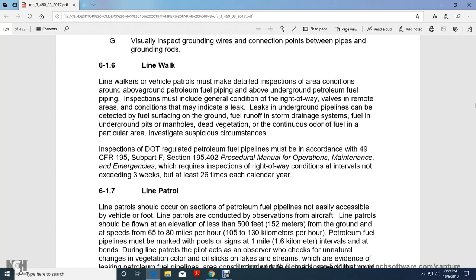Inspection must include the general condition of the valve and the remote area. Conditions that may indicate a leak of the underground pipelines can be detected by fuel surfacing on the ground, fuel in the runoff, the storm drain system, fuel in underground pits with the manhole, dead vegetation, or a continuous odor of fuel in a particular area. Investigate suspicious circumstances.